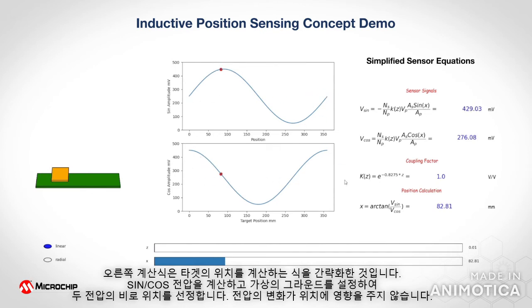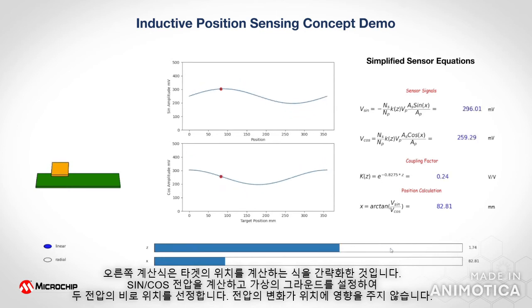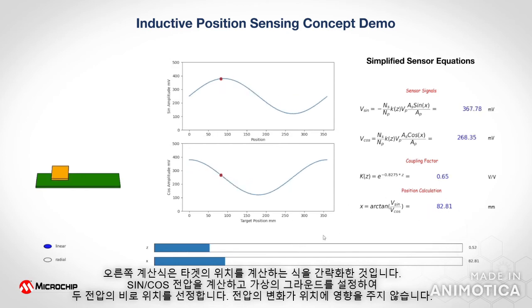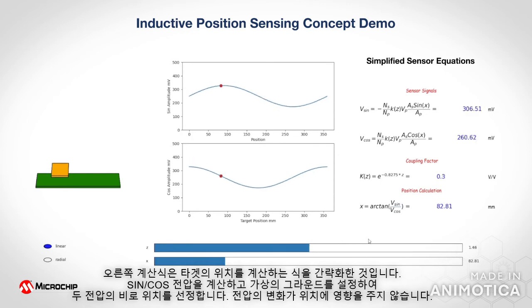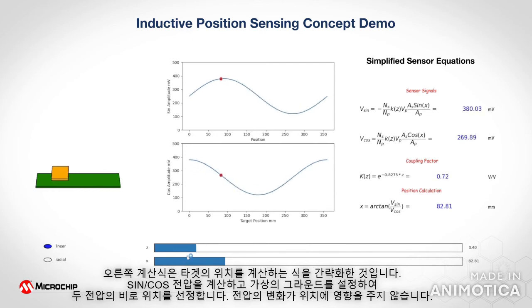The final thing to notice is that as we change the air gap, the position calculation does not really change. You might wonder, since the amplitude of the red dots is certainly changing, why doesn't the position change? This is because we're taking the ratio between the two signals, and these signals increase and decrease at the same amplitude and rate based on the sensor - these are essentially common mode signals.